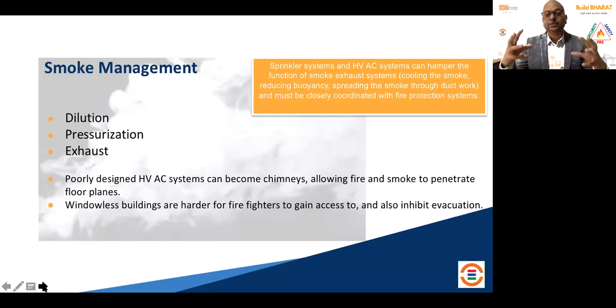Pressurization means you inject fresh air externally into the confined area, building that area to a higher pressure than the adjoining area, so that smoke will not enter it. Specifically, stairwell pressurization means the stairwell, being the safest and most critical area of the building, must be smoke free at all times, especially during a fire. You inject air to create positive pressure so that the adjoining lobby or corridor pressure is less than the stairwell pressure. Smoke always moves from high pressure to low, never low to high.